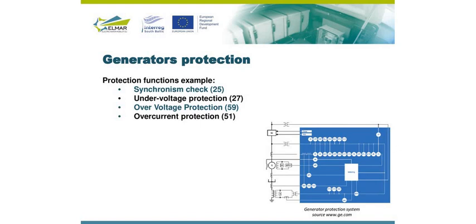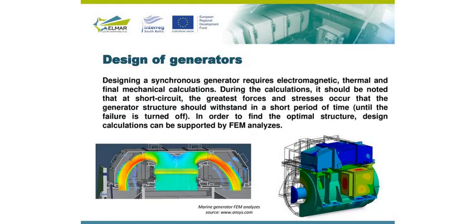So for the generator protection example, we can see functions of the protection. There is a synchronism check function, under voltage protection function, over voltage protection, and over current protection. For bigger generators, we need to have extended, more detailed functions.